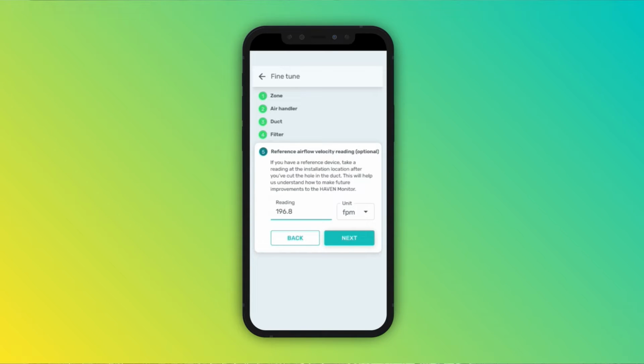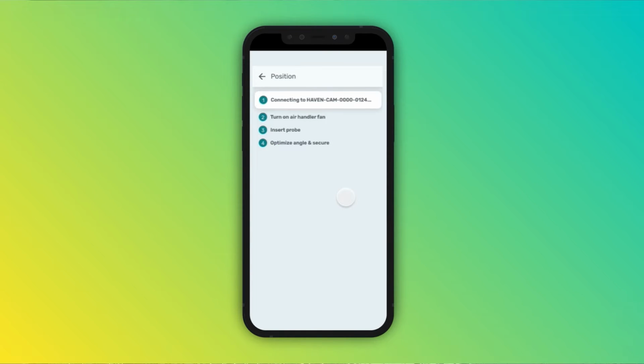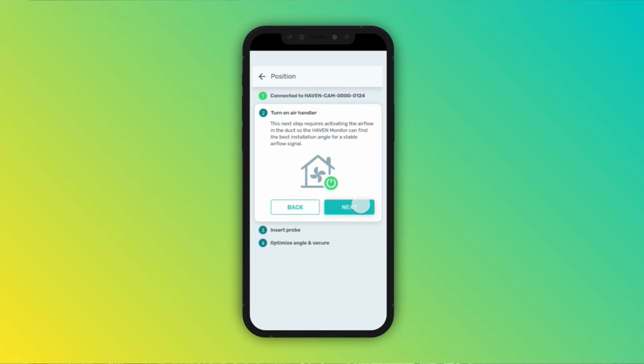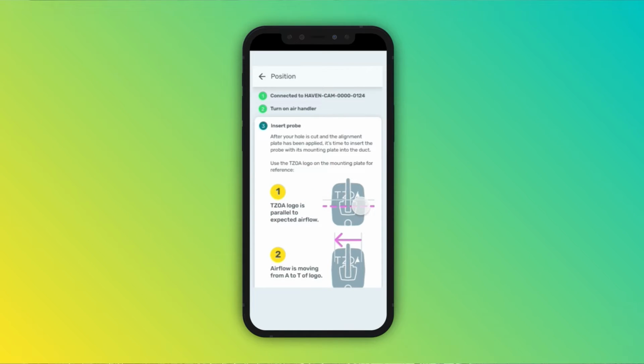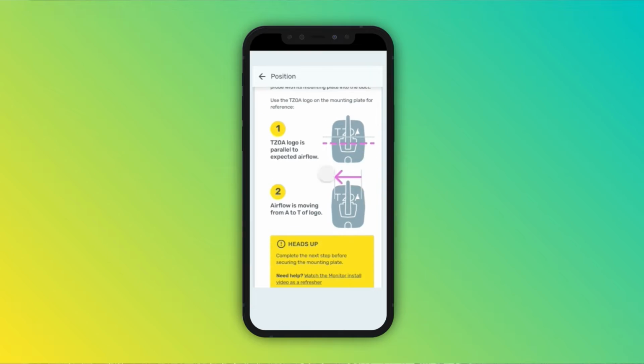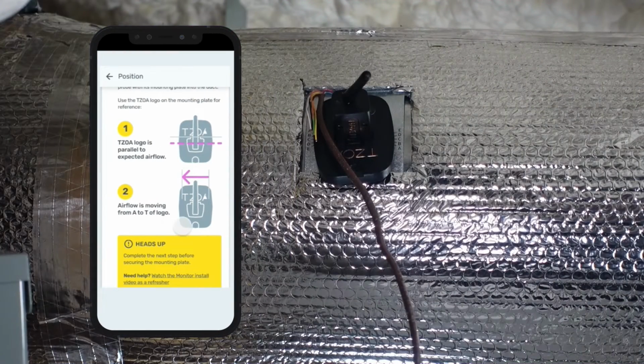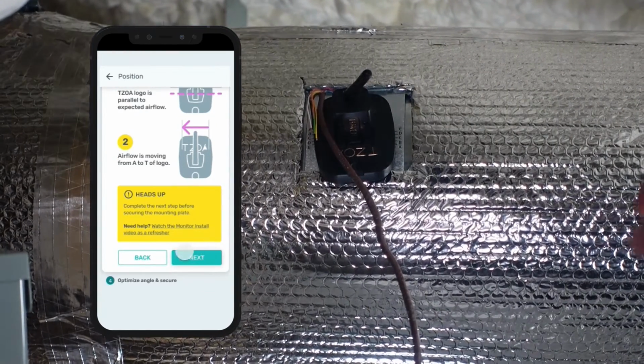When you arrive at the position step, the app will search for any powered Haven devices. Make sure you've activated the power source for the device at this point. The app should find and connect to the serial number of the device and remind you that the air handler needs to be on with the probe in position in the ductwork for the next step.